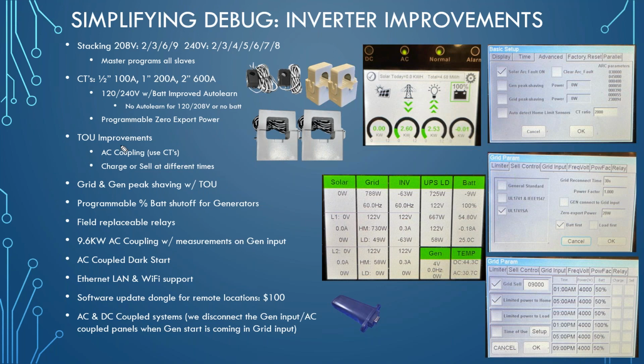If you have an undersized generator, we can use these CT sensors to measure how much power the generator is outputting. If maybe you have an 8 kW generator and you don't want to pull more than 6 kW to the home, you can have the Sol-Ark sync up to the generator while it's running. If your loads in the house exceed 6 kW, the inverter will stop charging the battery and start discharging the battery to help out momentarily for whatever that load was that went above your threshold value, which is really handy.